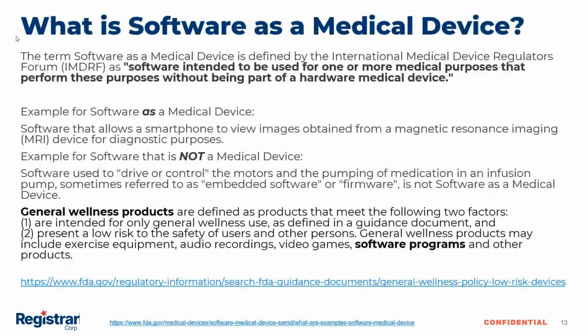And I would also like to talk a little bit about software. Software is also a complicated topic, and the devil lies in the detail. So I'd like to start with when software is really called a medical device. What's the definition of that? By the International Medical Device Regulators Forum, it is software intended to be used for one or more medical purposes that perform these purposes without being part of a hardware medical device.